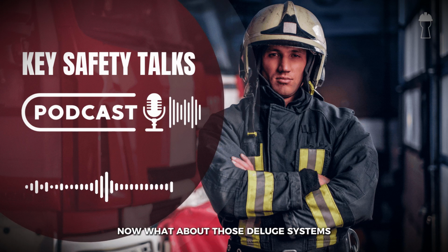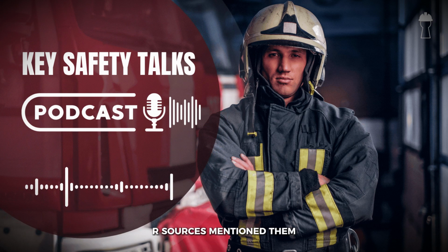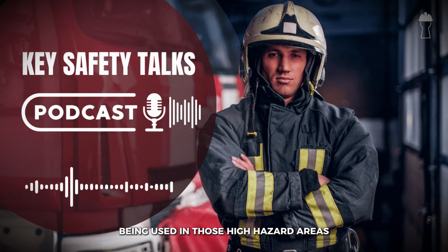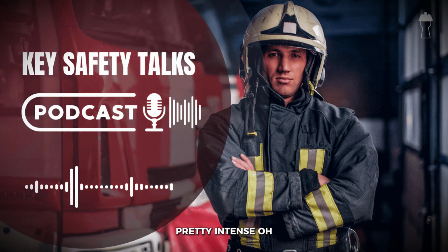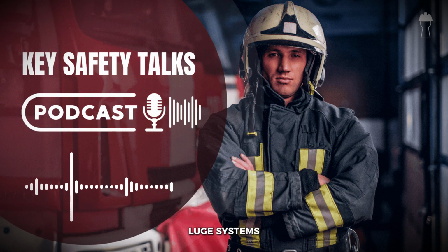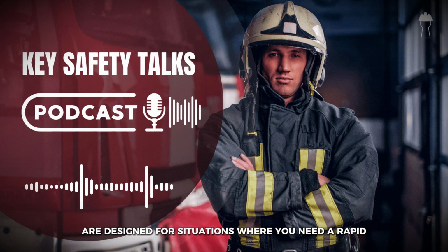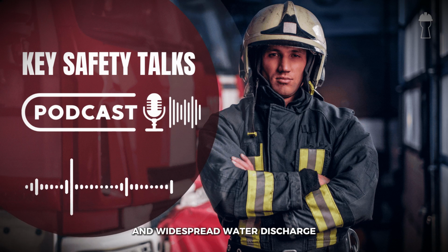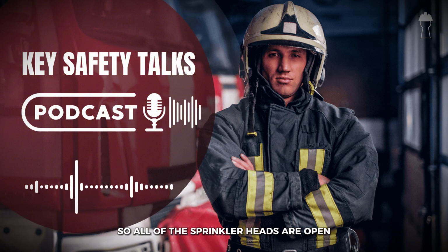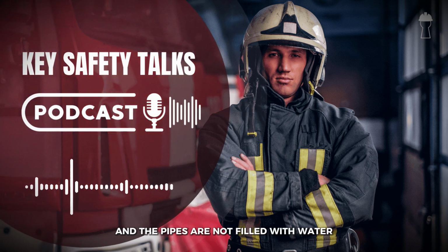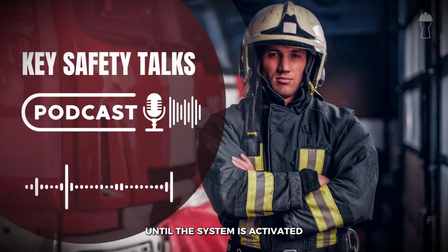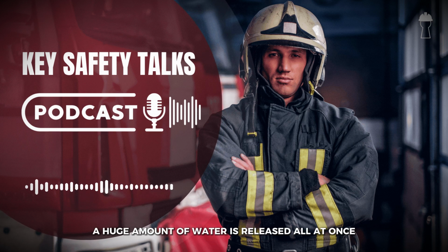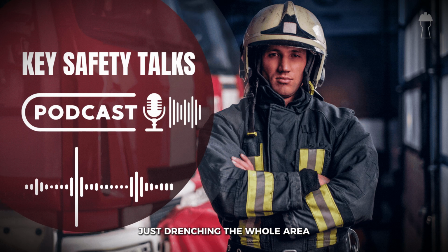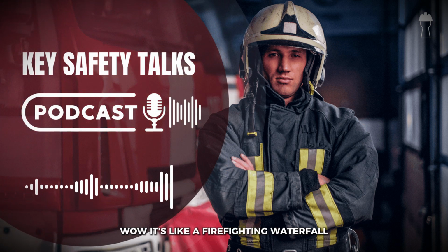Now, what about those deluge systems? Our sources mentioned them being used in those high-hazard areas. They sound pretty intense. Oh, they are. Deluge systems are designed for situations where you need a rapid and widespread water discharge. So all of the sprinkler heads are open, and the pipes are not filled with water until the system is activated. So when a fire is detected, a huge amount of water is released all at once, just drenching the whole area. Wow, it's like a firefighting waterfall.